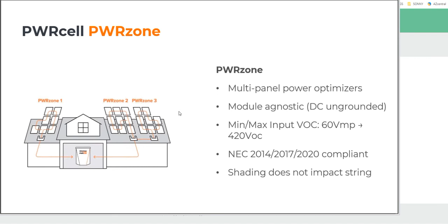We can tie up to 6 of these to a single inverter. So we can literally do a 2-to-1 DC to AC ratio on our inverters. So up to 15 kilowatts of PV on a single 7.6. I know that sounds like crazy design practice, but if you've got a lot of battery tied to it, then you may have a place to put it. So it's something we can do.